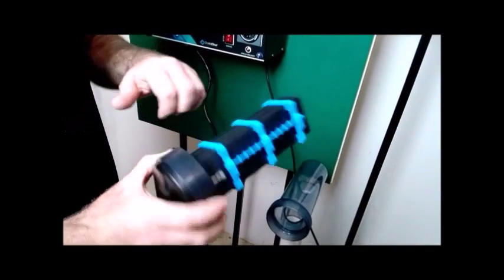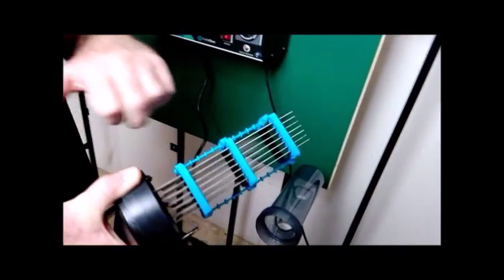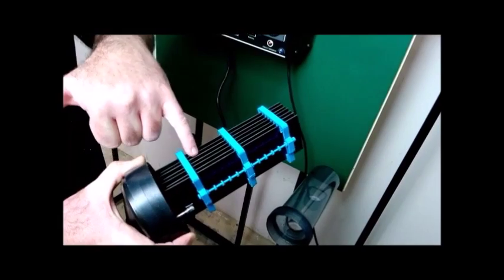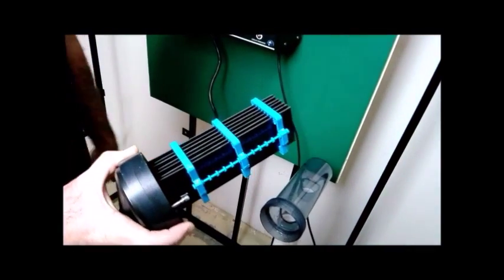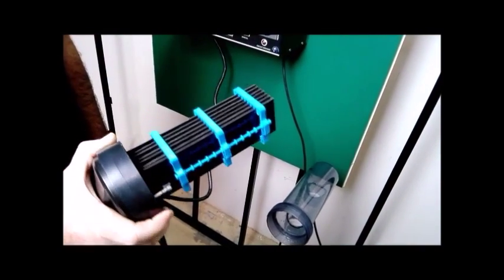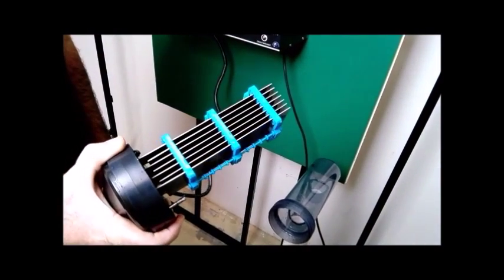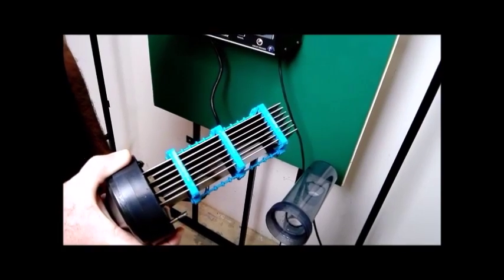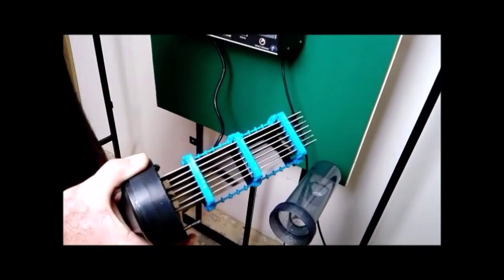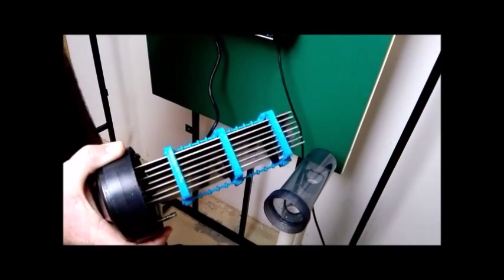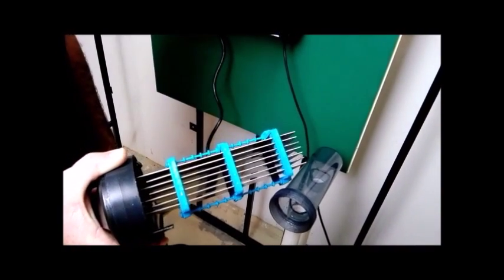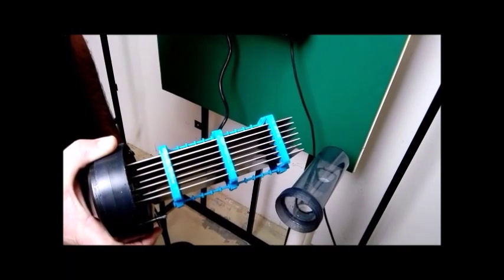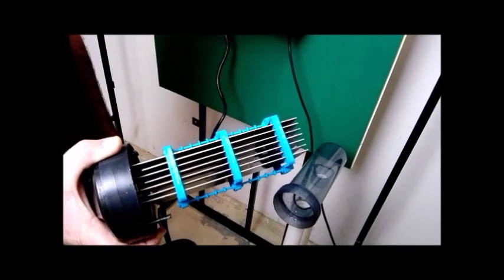Check the outer side of the plates and in between the plates. If there is excessive build-up, put the cell into a solution of one part hydrochloric acid to 10 parts water and leave to clean for approximately 10 minutes.